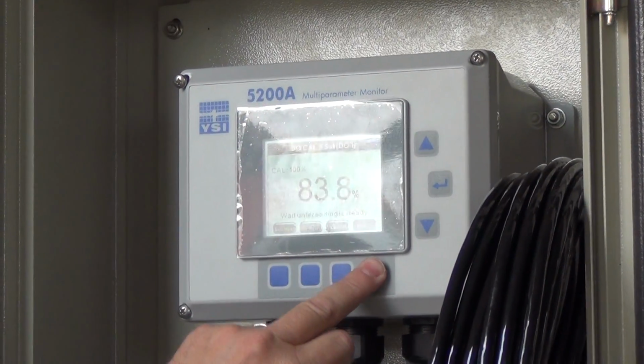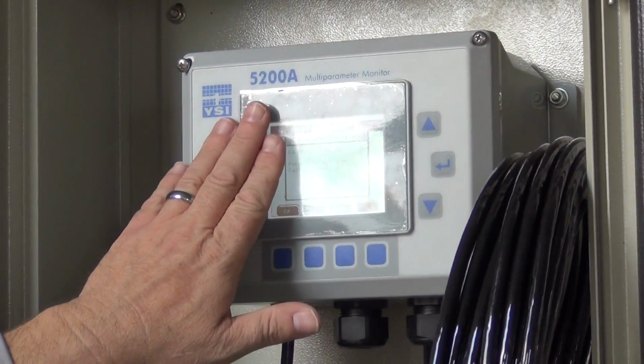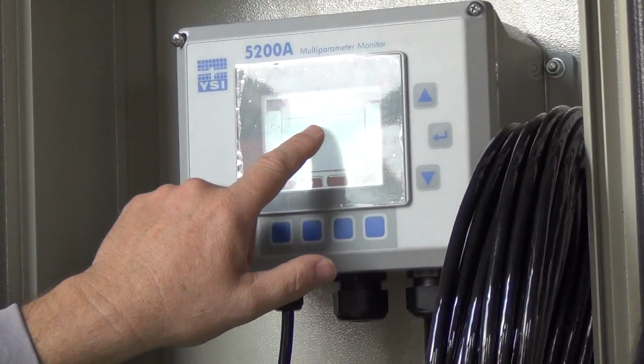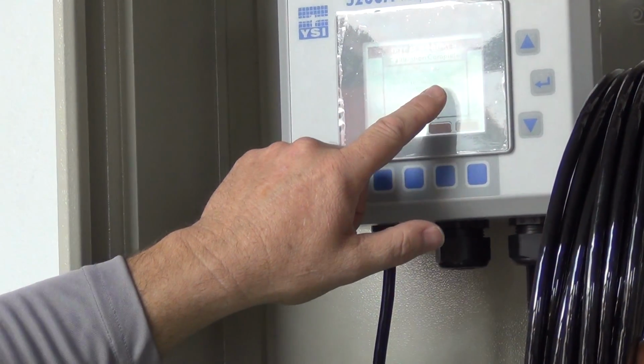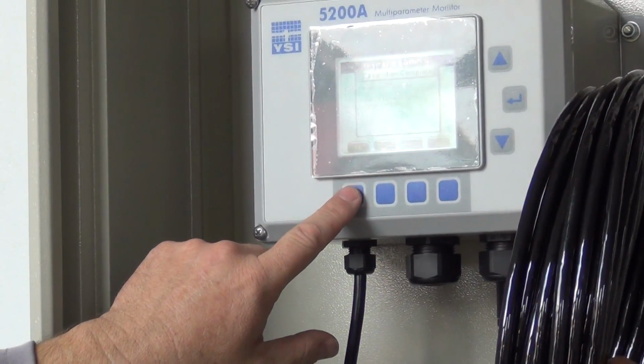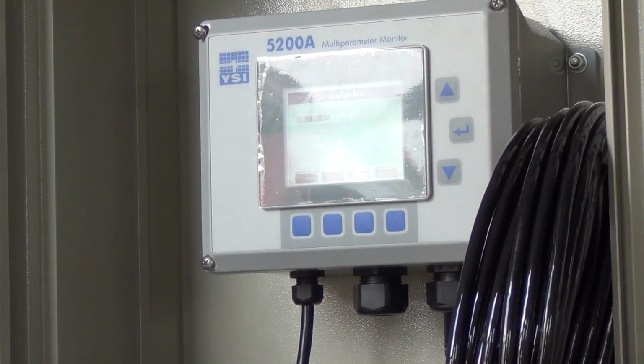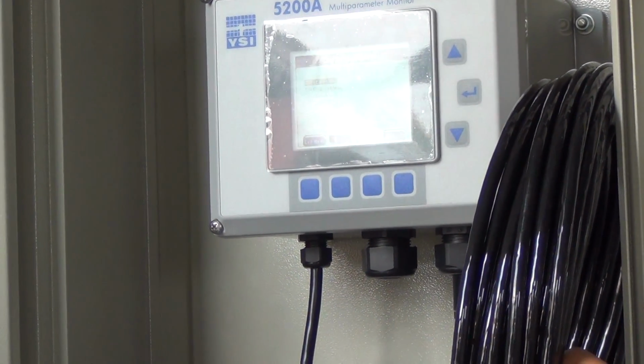I push next. If everything is okay, calibration complete. Calibration is complete. Press OK to return to the main calibration menu. It has now calibrated the DO that easy.